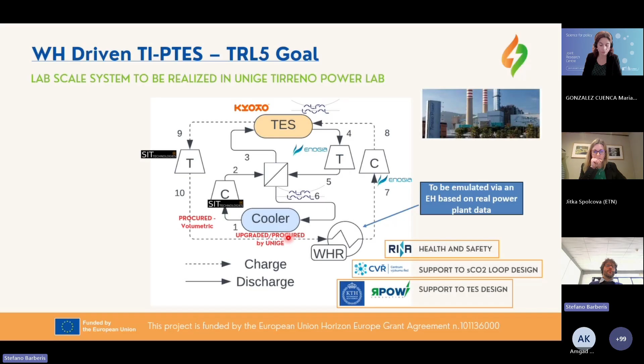In parallel, this charging cycle is composed by some volumetric compressor that we are adapting from off-the-shelf refrigeration components, a recuperator provided by Alfa Laval, and then we go up to the thermal energy storage to release the heat and take advantage of it to expand the supercritical CO2 in the turbine and close the cycle thanks to a cooler.